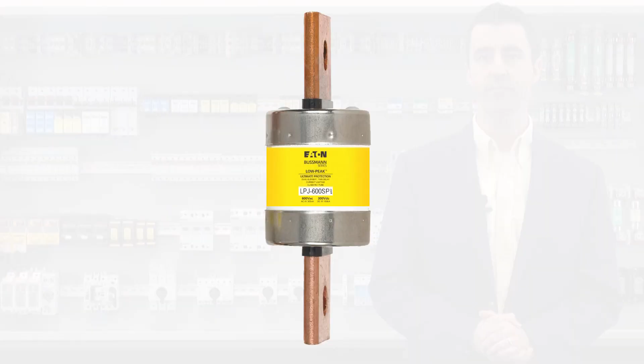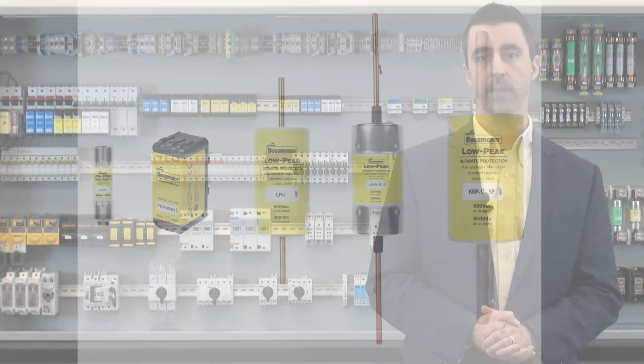Arcing faults can release extreme amounts of energy and destroy equipment and put workers in very unsafe situations. The overcurrent protective device characteristics play an important role in this outcome. Current limiting overcurrent protective devices, such as Low-Peak fuses, when operating in their current limiting range, not only reduce the peak current, but also reduce the time duration current is allowed to flow, thereby potentially reducing the hazards. Current limiting devices may not entirely mitigate the potential hazards, especially when the device is 1200 amps or greater and the available fault current is low.